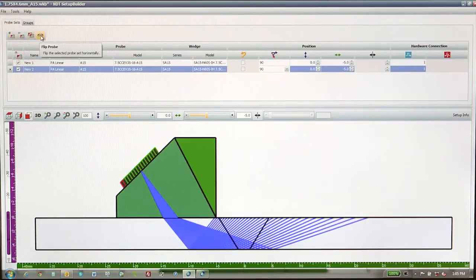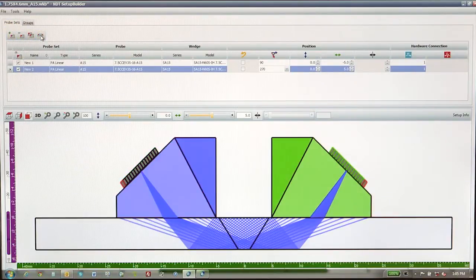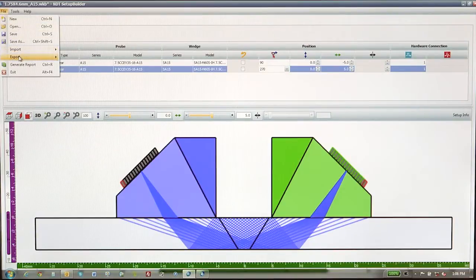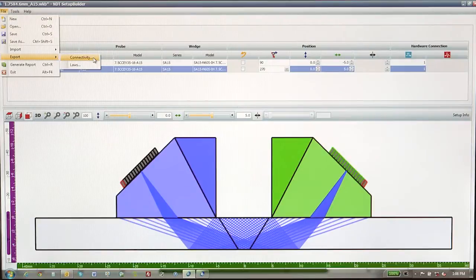The inspection is performed from both sides of the weld using two probes perpendicular to the weld line and secured at the predetermined position in the scanner relative to the weld centerline. This scan plan along with the probe, wedge, and beam parameters are typically included in a technique sheet that is included with the inspection report.